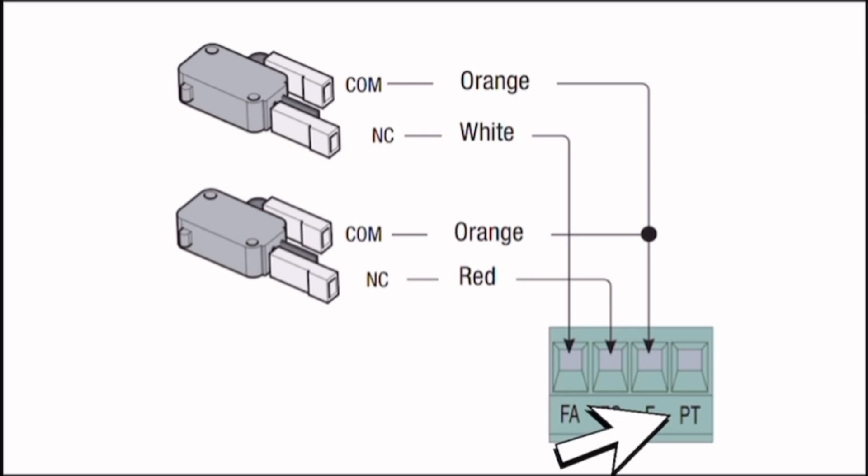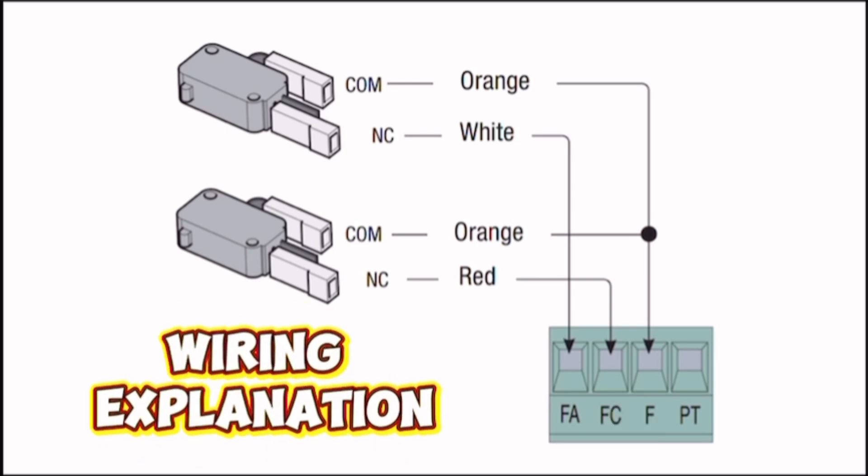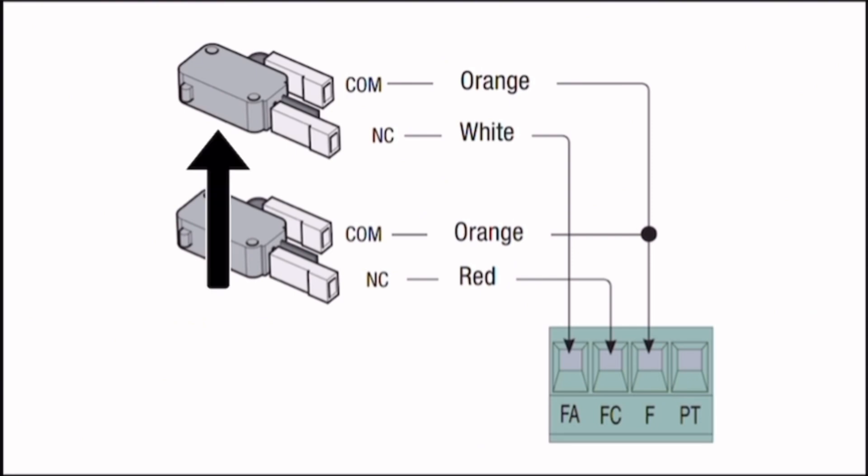P.T. - Additional Terminal for Accessories or Sensors. Wiring Explanation: Upper Limit Switch Open Position - The COM (orange wire) connects to the same F terminal on the control board. The NC (white wire) connects to the F.A. terminal, representing the fully open position.